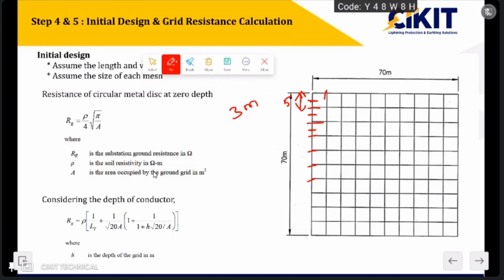Again I have to perform this calculation, find the step and touch voltages, and compare them with the tolerable limit for ensuring safety. The final design will be achieved only if the calculated step and touch voltages are less than the tolerable values. The entire calculation has begun by assuming that a circular disc is placed on the surface of the earth. The basis for this entire calculation is a circular metal disc placed at zero depth. From this assumption only they have derived this entire formula.